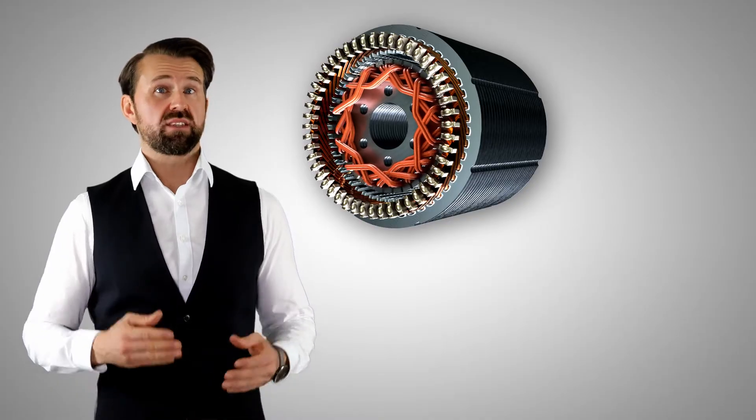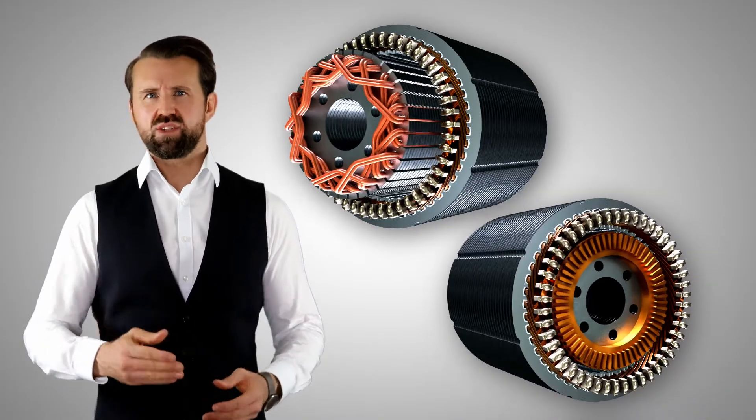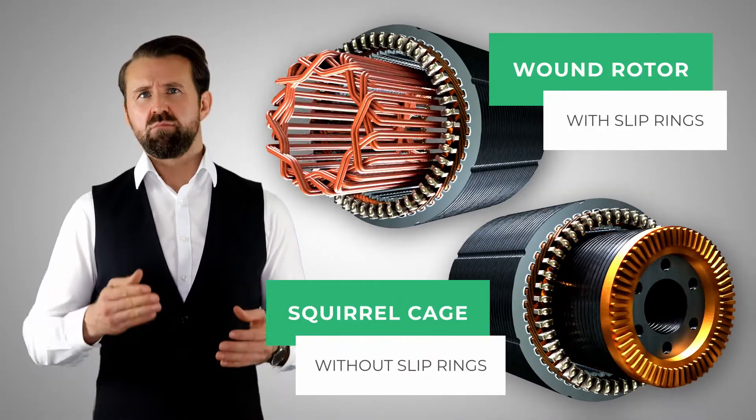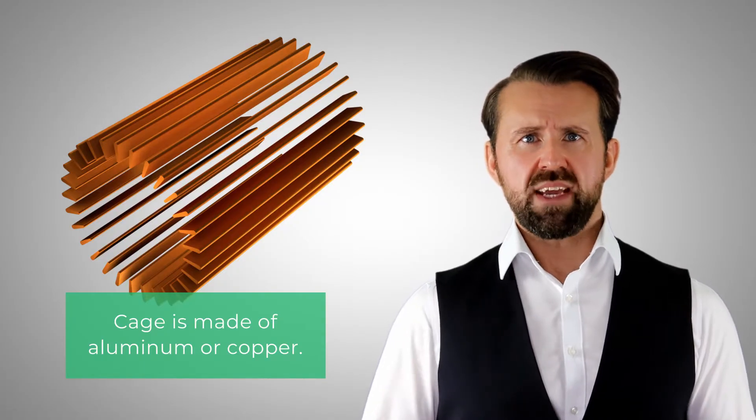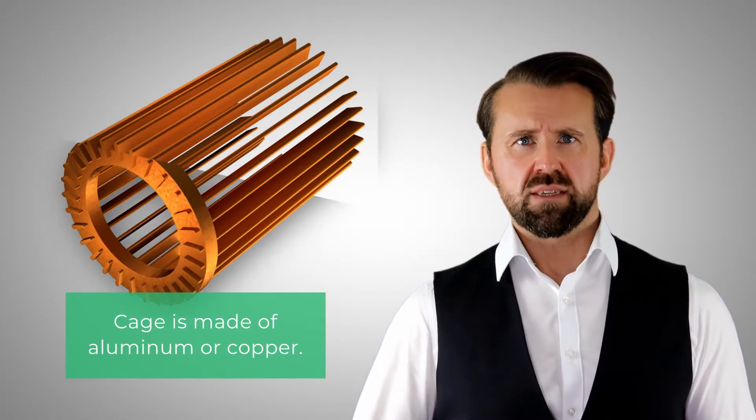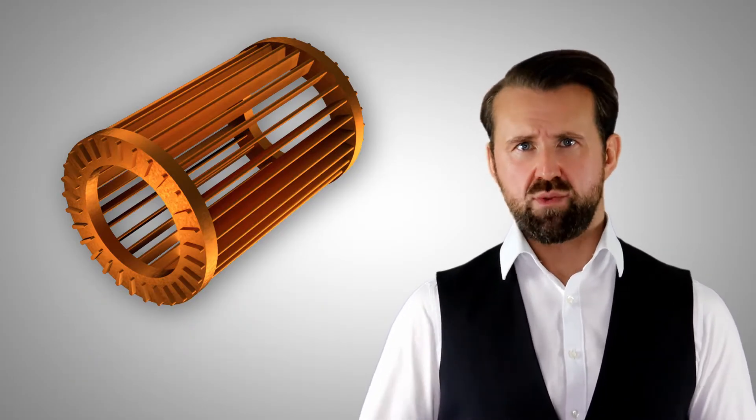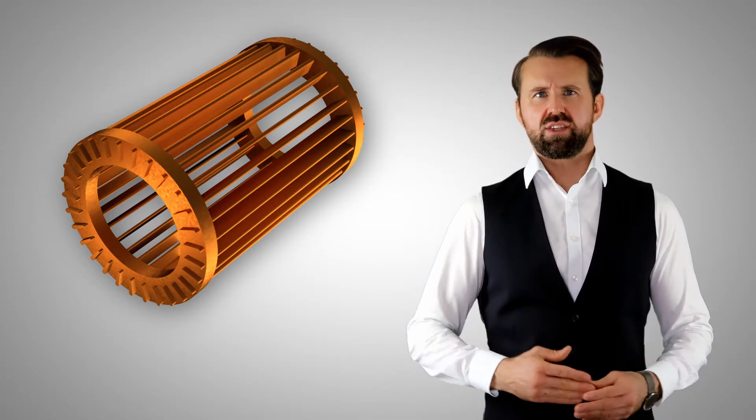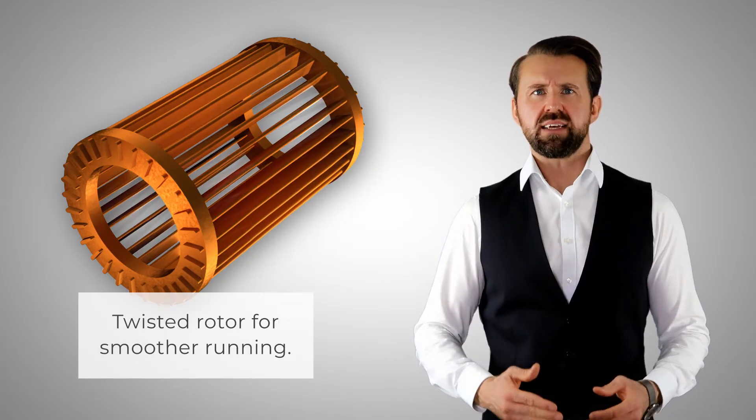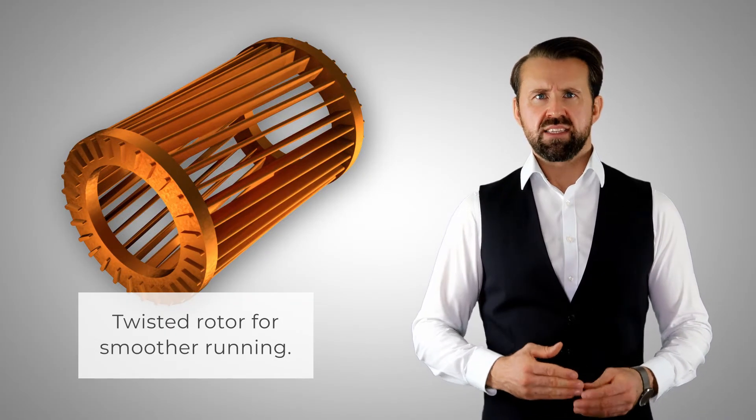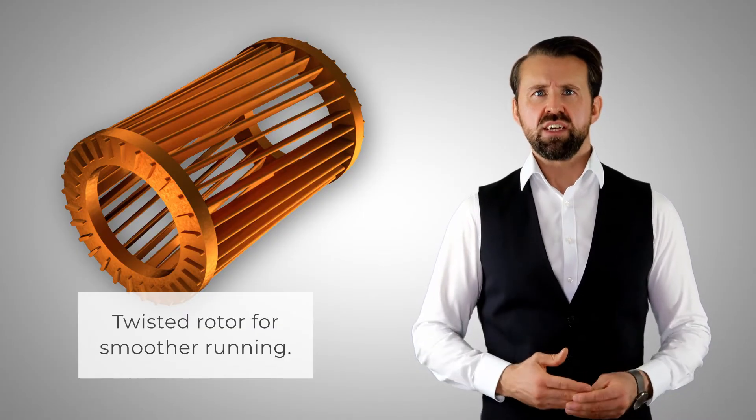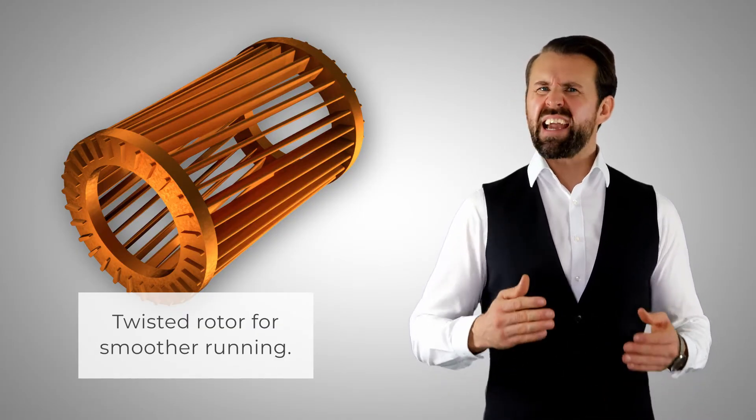Induction motors can be divided into two different types: one with slip ring rotor and one with squirrel cage rotor, which is used in more than 90% of the applications. The squirrel cage rotor consists of a cage of bars which are made of aluminum or copper. The bars are short-circuited at the upper and lower ends with rings of the same material. To reduce torque oscillations from the rotor, the bars and the plates are usually slightly twisted. This also has the advantage that the rotor runs quieter and smoother.